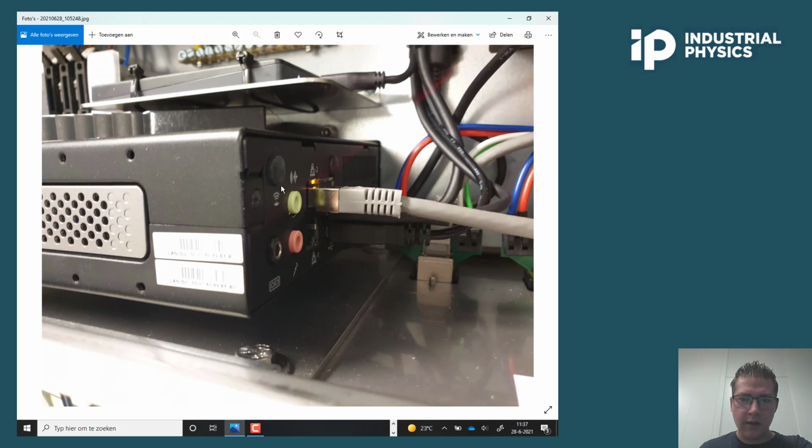Also, this Ethernet port is very important. On the PC itself there are 2 Ethernet ports, a top one and a bottom one. This is the correct setup. So the Ethernet cable should always be connected into the top Ethernet port. The bottom one is an undefined Ethernet port and is used either for failsafe, if that's an addition on the system, or it is used for a VPN connection or a remote TeamViewer connection. So this Ethernet port is not set up correctly with the static IP addresses.